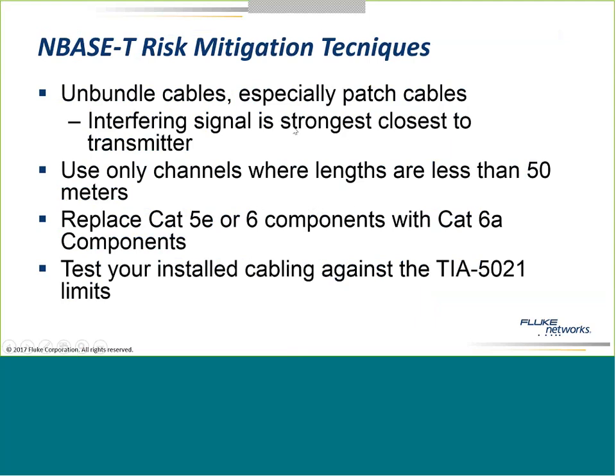Ways to reduce the potential for alien crosstalk: unbundle the cables, especially the patch cables — the signal is strongest right out of the NIC and weakest and most attenuated at the far end. Only use channels where lengths are less than 50 meters, so we don't have a chance to generate that noise. Replace some 5E and 6 components with 6A components — use 6A patch cords, use 6A jacks to reduce crosstalk. Test it: within the latest revision of our firmware you'll see a test for 2.5 and 5GBASE-T per TIA-5021.